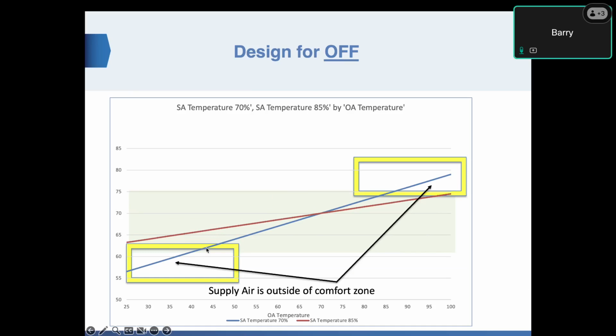So anything below 43 degrees outside, you're going to be bringing in air below 62 degrees. You may be looking at doing post-heating or having to run the heating system continuously to manage that. At 85%, instead of 43 degrees as the point where you fall out of that below 62, it goes all the way down to about 20 degrees here. So anything between 20 and 43 degrees, very high efficiency ventilation is bringing air in at a comfortable level.